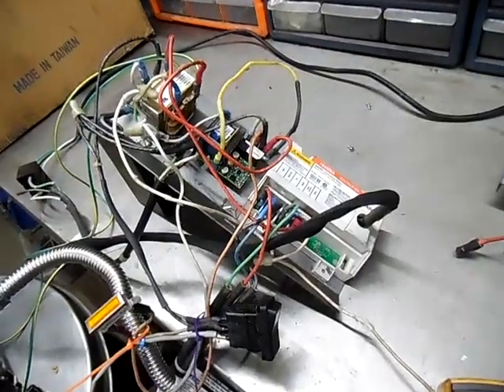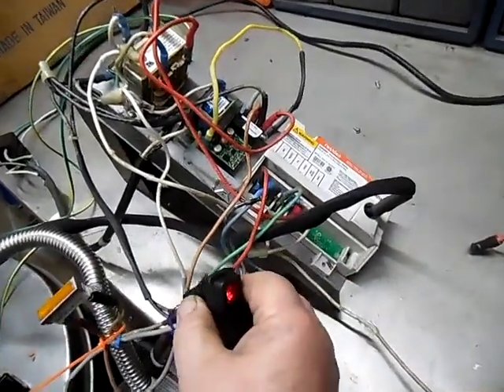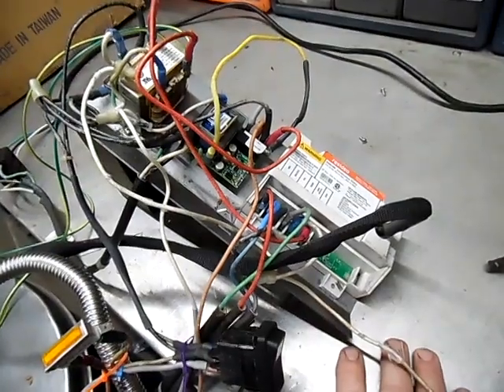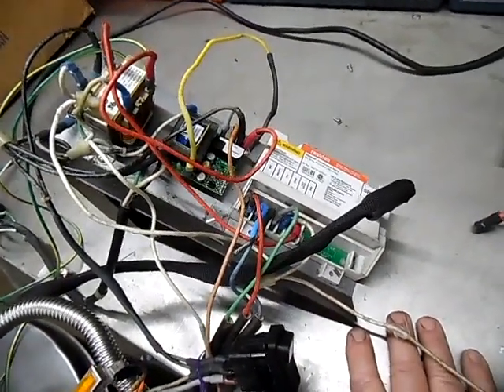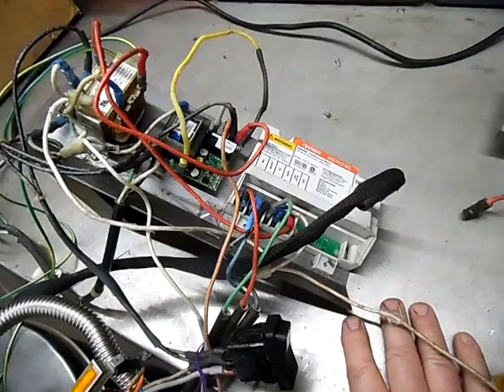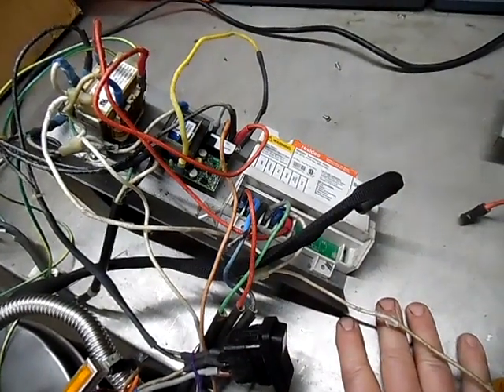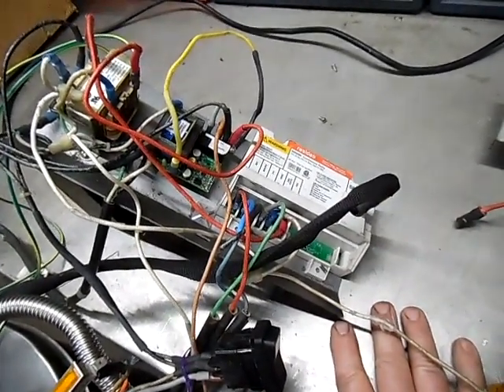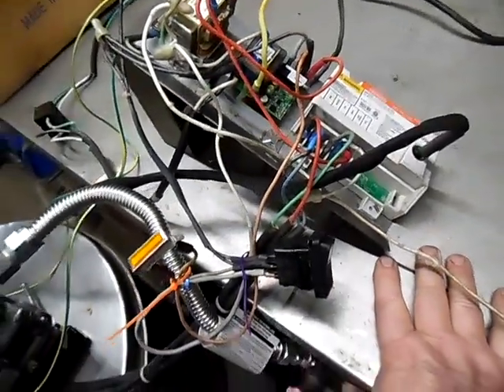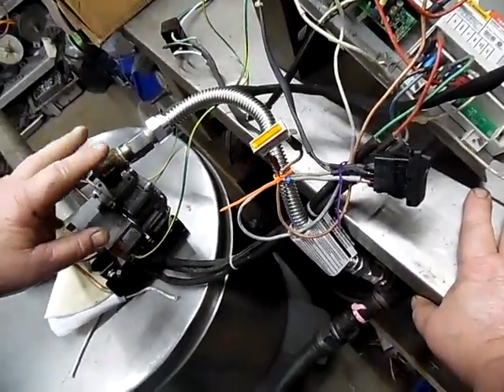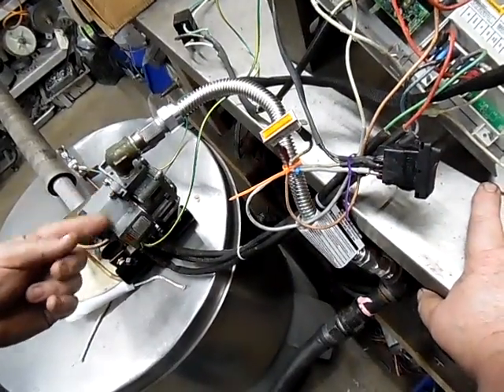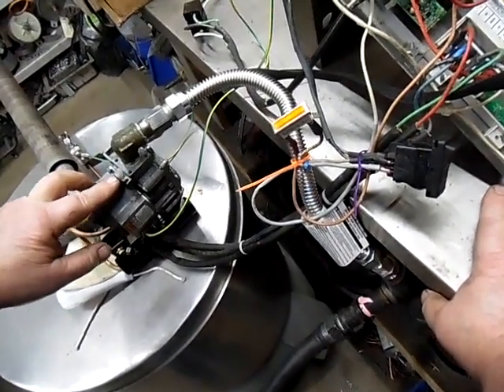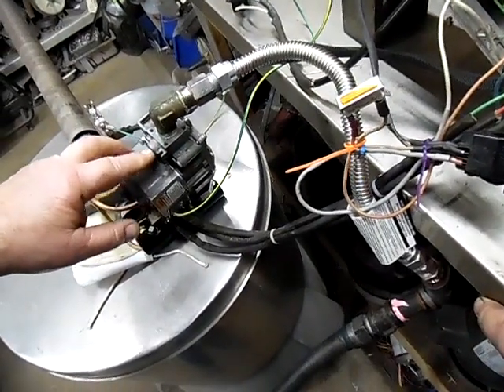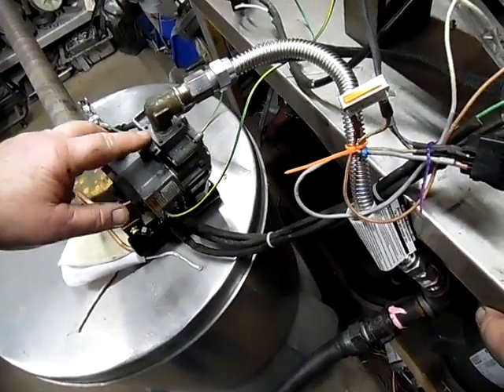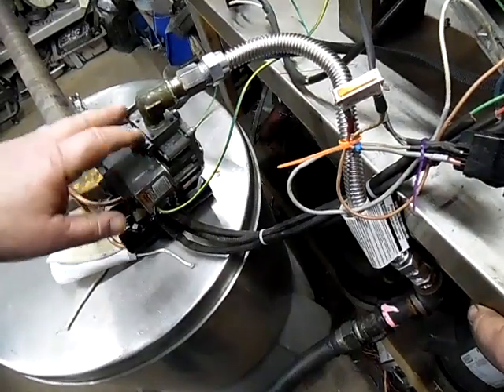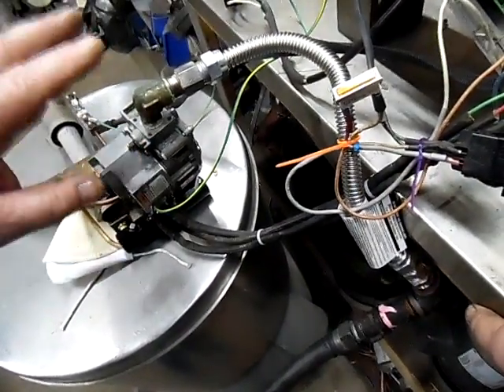The other thing I would tell people too, what I see a lot of with gas components, a lot of technicians are so used to working with them. Your good technicians today will put gauges on the gas valve. Just because your gas system's working fine in your building today does not mean it'll work fine tomorrow. Because as you add equipment, your gas pressures can change, your volume of gas can change, and that's why they put ports on the gas valve, so you can check and make sure your pressures and your volume are within manufacturer spec when this is running. And what I would suggest is run this machine, and if you've got 6 more, run all 6 at the same time and see if you see any drop.